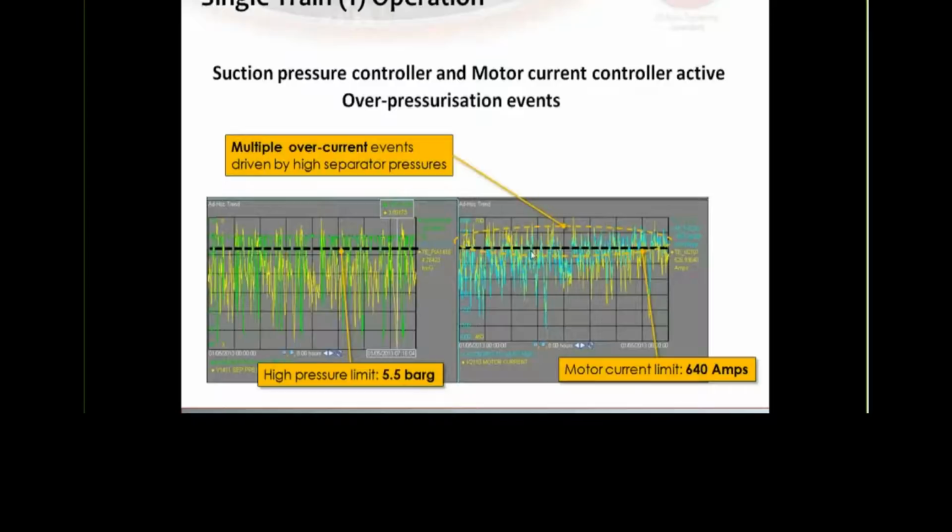So with the same amount of wells running, train 1 does have higher production, but what ends up happening is that it keeps constantly hitting the power limit. The approach was always to have a similar set of wells running when they're both in single train operation to make operations slightly easier, but this is one thing that was neglected during that process.